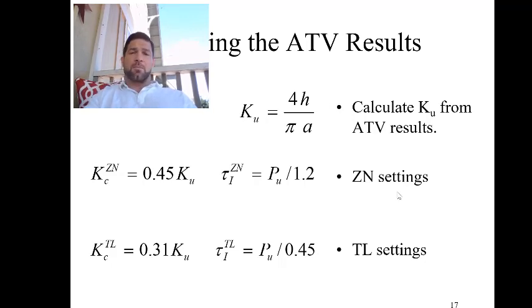There's two different types of settings that can be used with this. Generally we have what's called ZN settings. These settings are typically applied for systems where you want a little bit more of an aggressive controller tuning, so maybe a quarter amplitude to a fifth amplitude decay controller settings. We can also use the TL which is Tyreus-Luyben settings. And these are typically used for a more conservatively tuned controller where you don't want the system to respond as fast, because potentially maybe it's a non-linear system or you expect large disturbances that can affect the process.